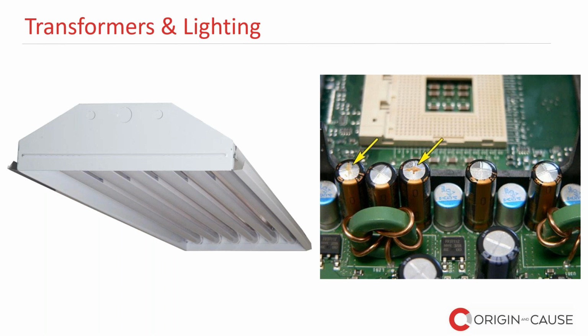A similar issue can occur when newer lighting, like the left photo, is not properly rated and installed into an electrical system. Capacitors on the circuit boards of such lighting fixtures may draw excessive current and vent due to harmonics, as seen in the photo on the right. So again, if we look at this photo on the right, where the arrows are, this is the venting that occurred right there and there. Unfortunately, all these types of losses don't come with nice arrows pointing to the failure mechanism that resulted in the fire or failure. It is essential to leave the evidence untouched and get yourself a forensic investigator to go through all the evidence with a fine-tooth comb.